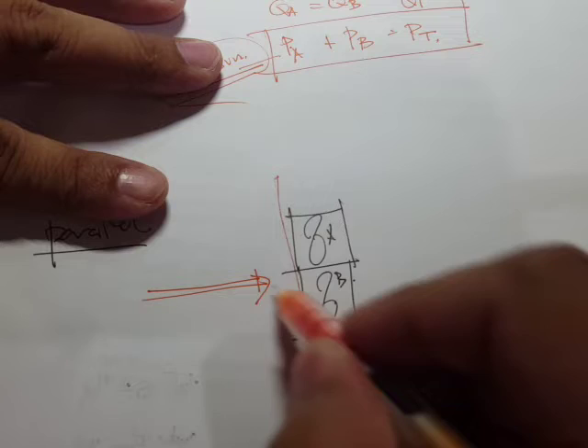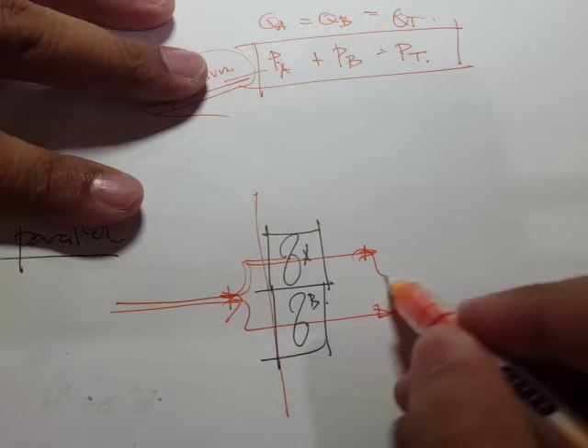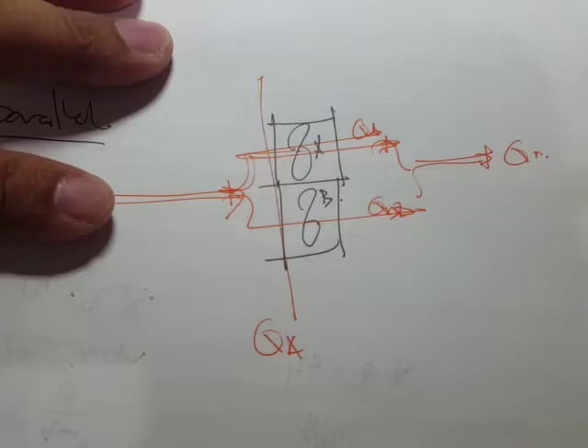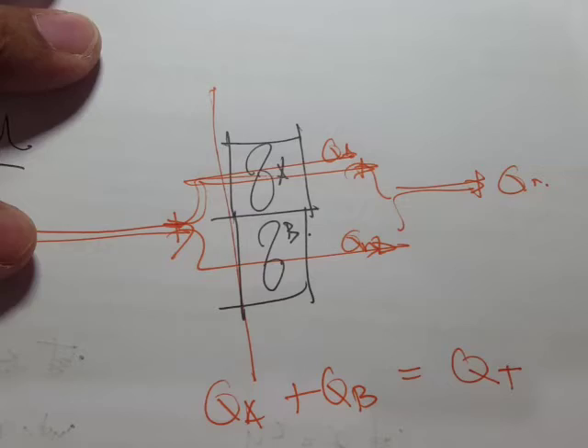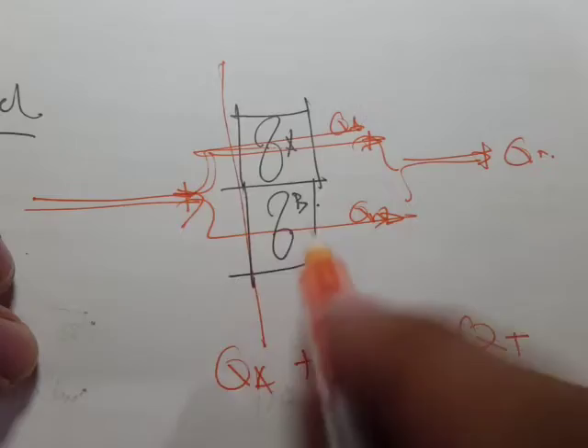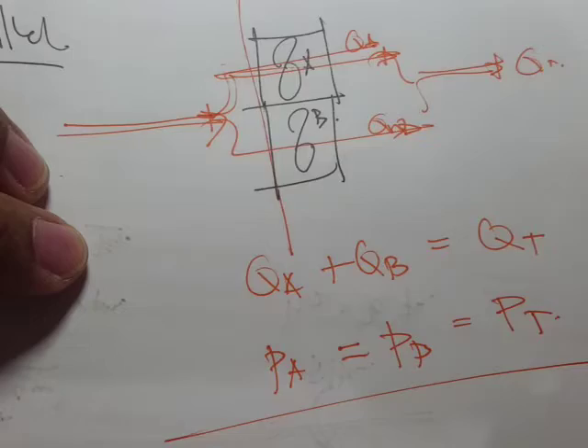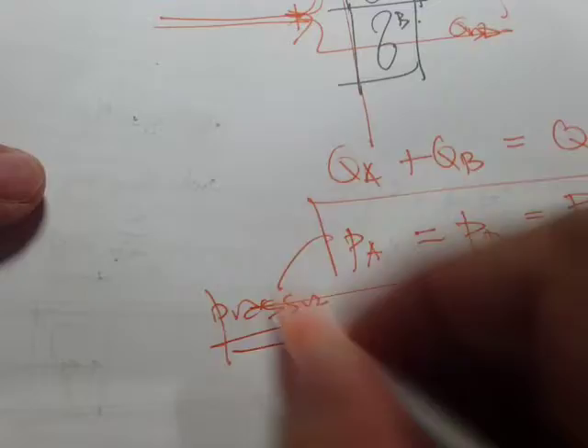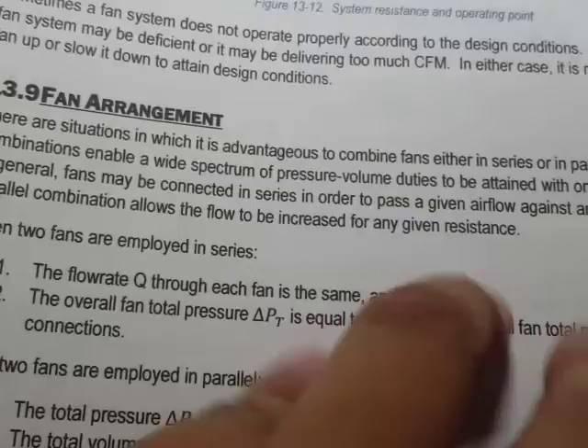For parallel arrangement, the airflow splits — part enters fan A and part enters fan B. The total flow rate is Q_A plus Q_B, which increases the overall flow rate. However, the pressure of fan A equals the pressure of fan B and equals the total pressure, so static pressure does not increase.